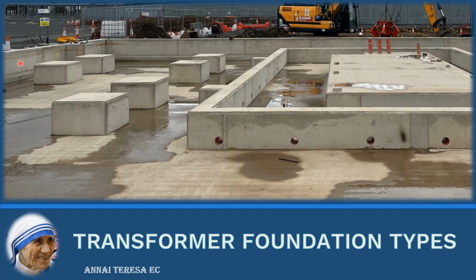After that, there is a bund wall around the transformer periphery, including the cooler bank supports. This is for oil containment, as the transformer size is very big with a high capacity of oil, so the oil containment is also very big for this transformer.